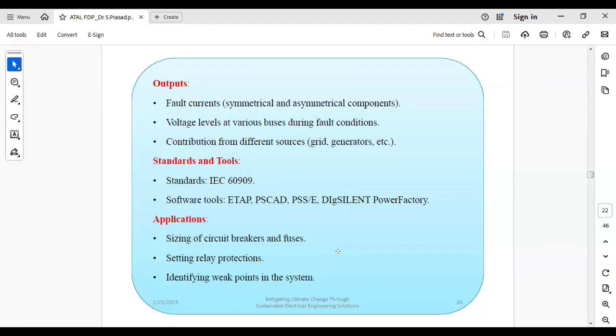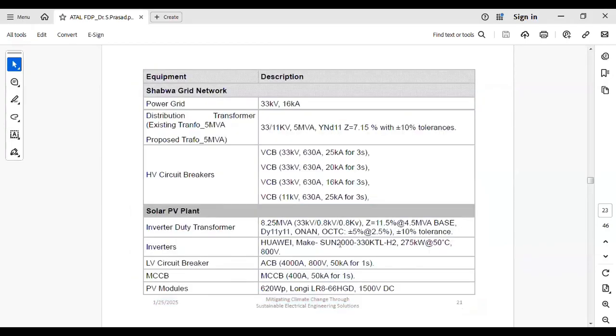Basically, to decide the size of the fuse or circuit breaker, MCCB, that has to be decided based upon the short circuit analysis. Okay, and setting relay protection. That means when you are going to coordinate the relays, the protecting devices, at the minimum fault current levels we are fixing it. So therefore, you have to conduct the short circuit analysis, and when you are going to integrate a solar PV system into the grid, this has to be done.